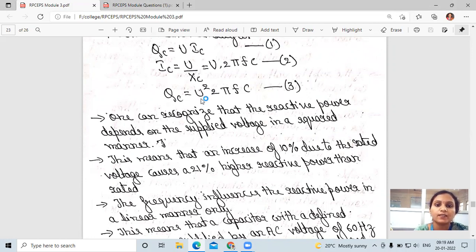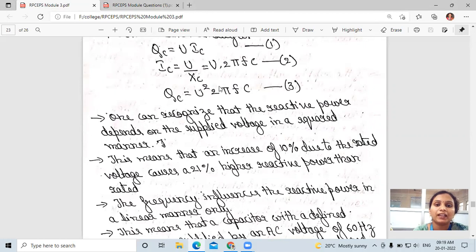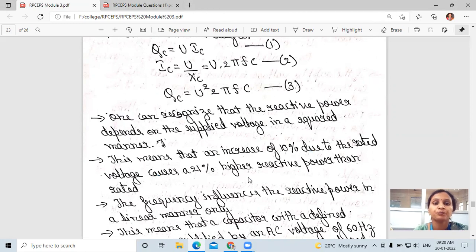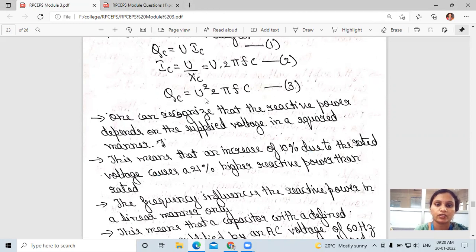One can recognize that reactive power depends on the supplied voltage in a squared manner. Qc is equal to U², that is voltage squared. This means that an increase of 10 percent in the rated voltage causes a 21 percent higher reactive power than rated, because the equation shows Qc is proportional to U².